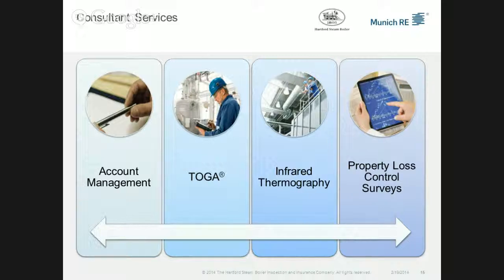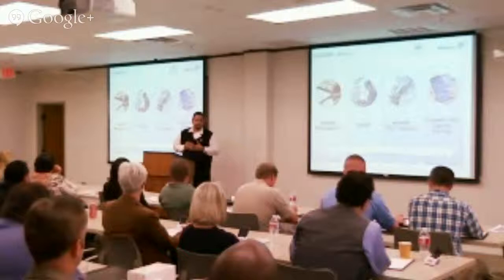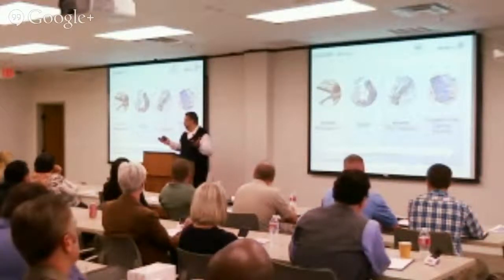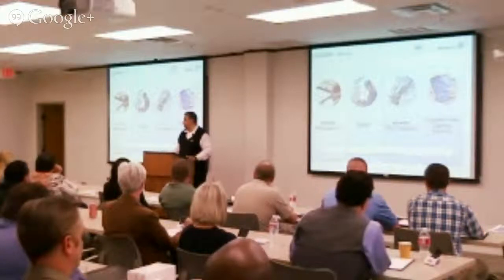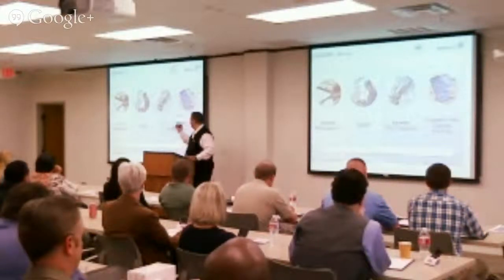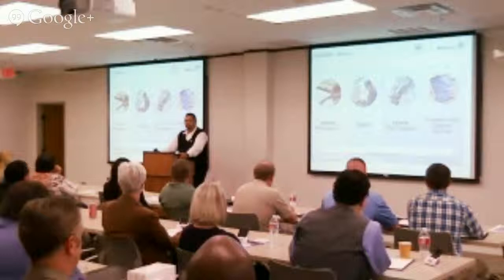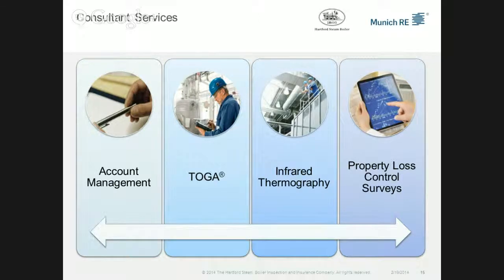About 90% of all electrical losses are preceded by an increase in temperature, so if you can catch that increase before it gets too far, you can help minimize the loss. I've done a lot of infrared inspections over the years, and I have yet to do one and not find something. You always find something in an infrared inspection.